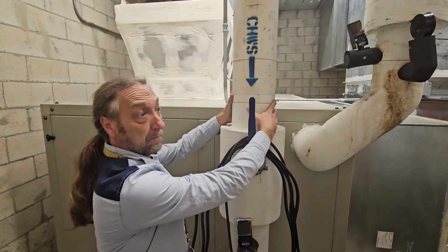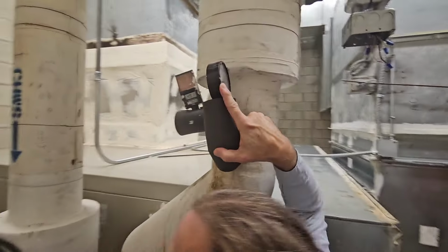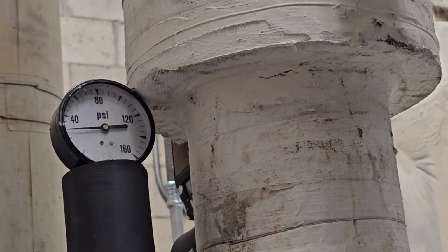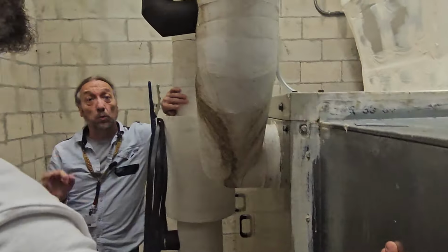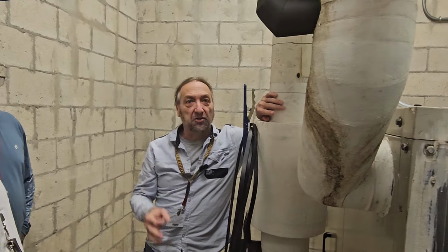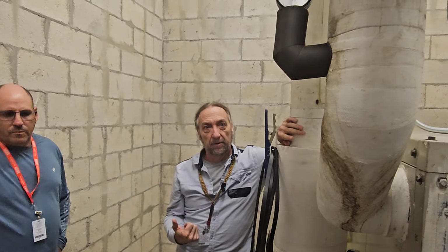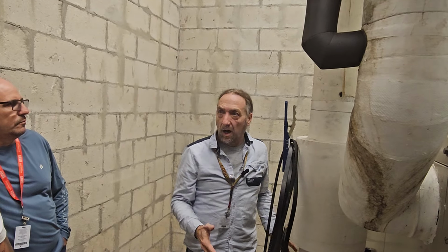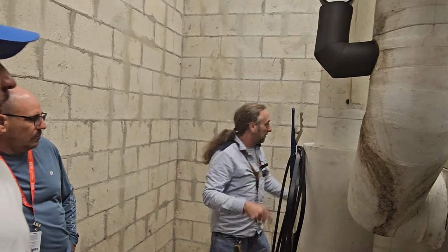Notice it's insulation. Okay? So they have a temperature here. And look at the temperature that this water is running at. Yeah, it's almost freezing, right? So there's a problem here with chillers. They run very close to freezing water temperature. And if the pump motor stops, you can freeze the water and break the evaporator. So the water pumps always have to be circulating. We need the fans to be on. Now, if the AC system shut off, the units out there shut off, but they almost never shut off. They're almost always running.